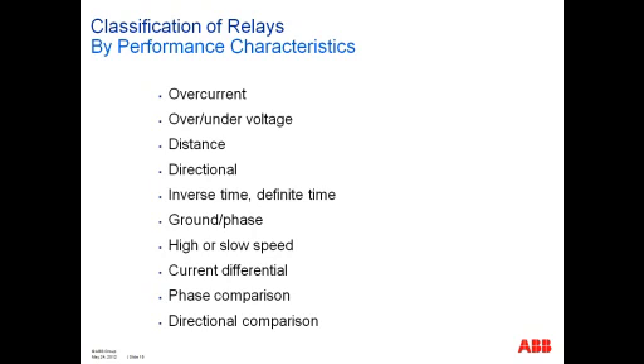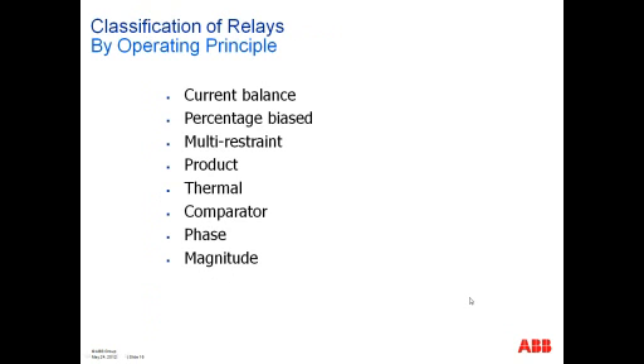You have classification of relays by performance characteristics, be them overcurrent, over/under voltage, distance, directional, inverse time, definite time, ground or phase, high or slow speed, current differential, phase comparison, directional comparison, and we'll talk about a number of these later. You have classification of relays by their operating principle, be them a current balance, whether they're percentage biased or multi-restraint devices. They could be a product, thermal, or some type of comparator, or let's call it a phasor comparator. Then you have phase or magnitude.